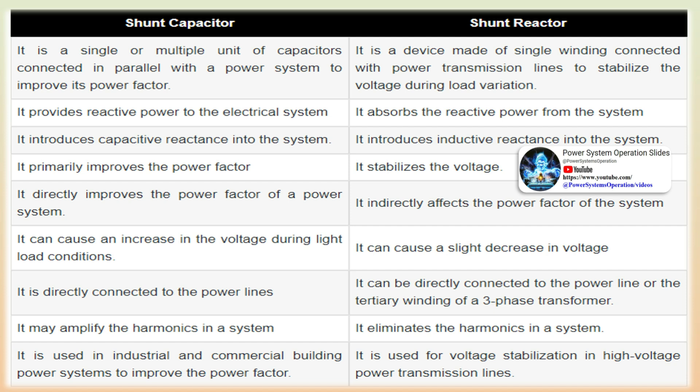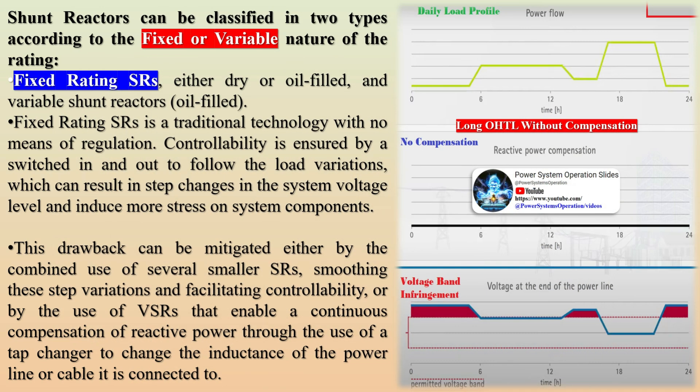Shunt reactors can be classified into two types according to the fixed or variable nature of their rating: fixed rating SRs (either dry or oil-filled) and variable shunt reactors (oil-filled). Fixed rating SRs represent a traditional technology with no means of regulation; controllability is ensured by switching in and out to follow load variations, which can result in step changes in the system voltage level and induce more stress on system components.